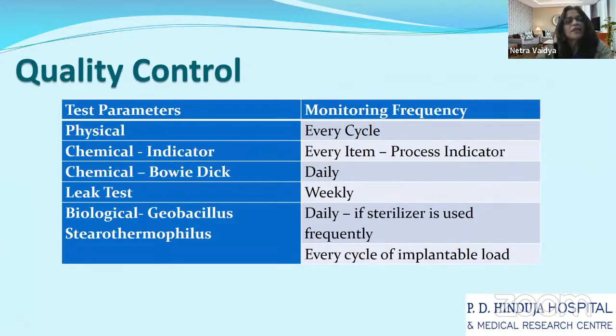So last is how do you ensure you have your quality control in place. These are the main quality control methods, wherein you check physical methods, wherein you check every cycle of the sterilizer. Recently we get printouts of your sterilization process, which talk about your pre-treatment, your sterilization hold time, and then your post-sterilization drying time. So you get to know whether your desired parameters have been met or not.